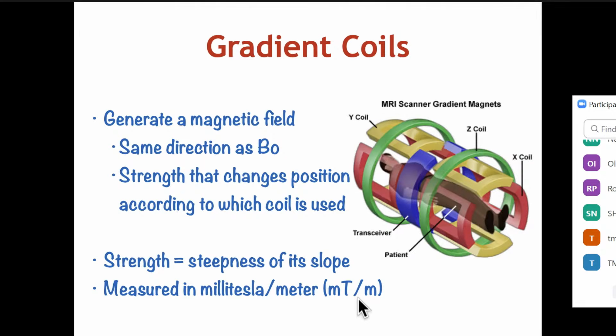The unit that's referred to for a gradient is basically millitesla per meter. And again, this is a specification of the specific scanner that you purchase. And then there's another concept called slew rate, which is basically a function of how fast the scanner is able to achieve this gradient. As we'll touch on later, it's the ability to alter the gradients, which is essential for being able to do MRI imaging.